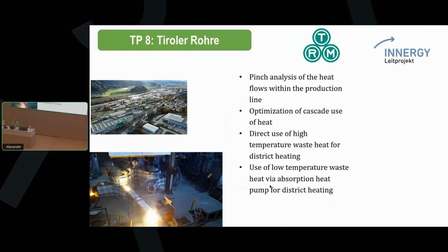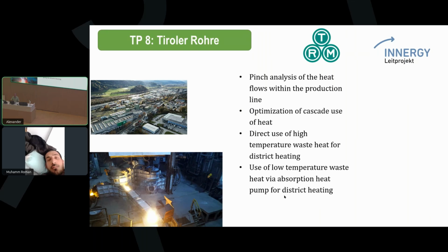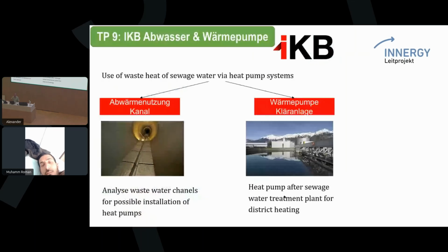Tiroler Rohre is a steel company, as I said. As you can already see here, quite high temperatures: they have exhaust gases at 400 to 500 degrees. With an air to water heat exchanger this can be used directly to feed into the district heating network. Low temperature heat can be used via an absorption heat pump. With the high temperature heat I can power an absorption heat pump, which takes low temperature waste heat at about 40 degrees and lifts it to around 85 to 90 degrees, and then this can also be used. So this is quite an interesting concept. Honestly, they have some problems, but this is always the case if you do something new, and we try to manage them.